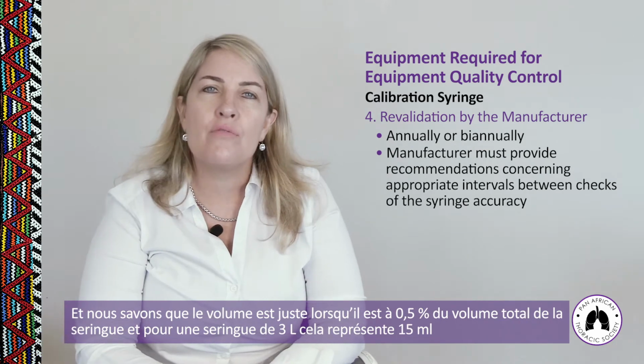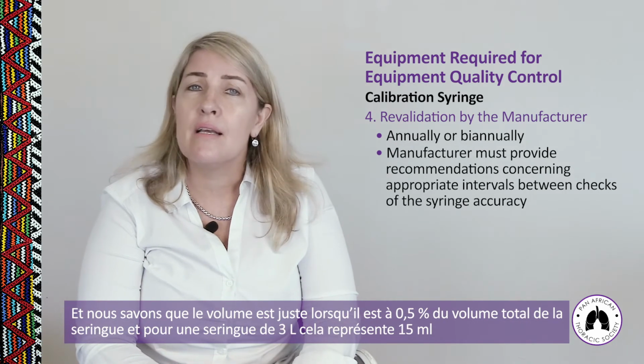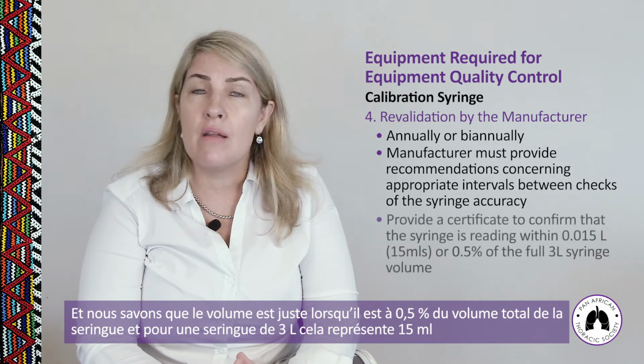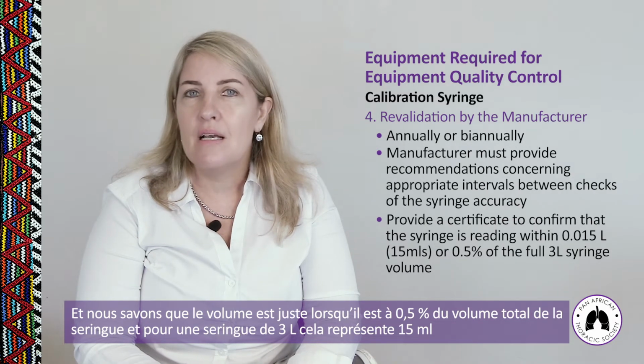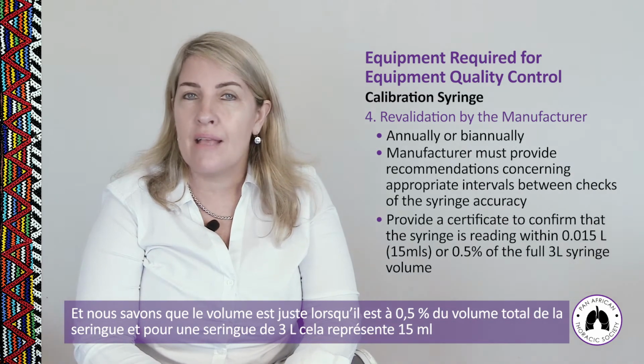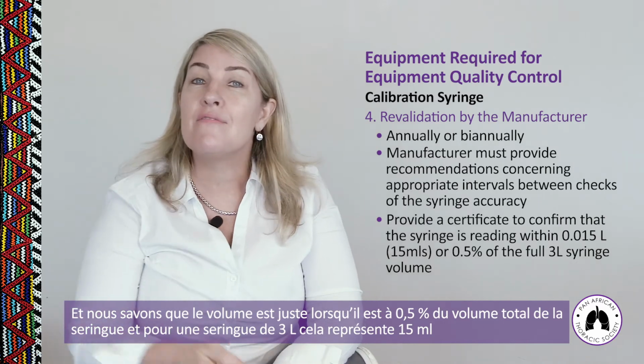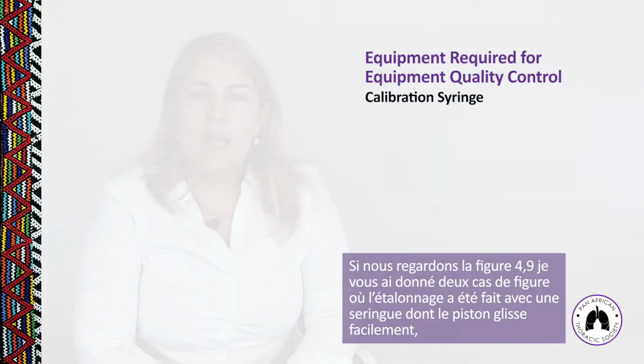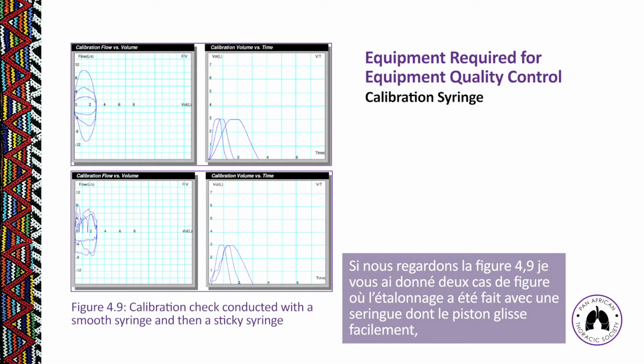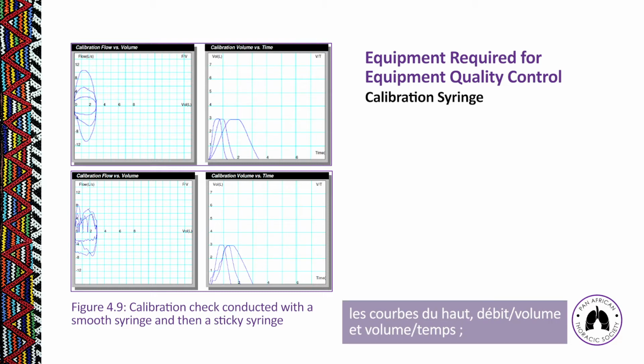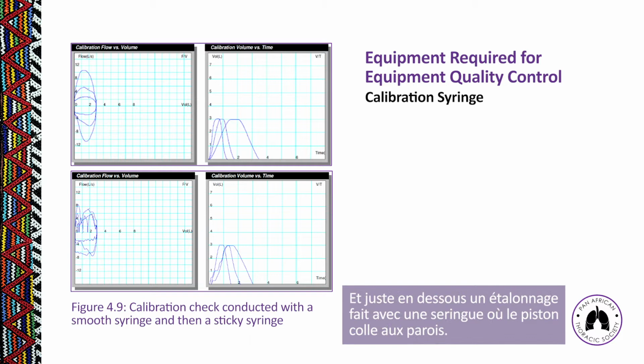And we know that a syringe volume is reading accurately when it has a volume of within 0.5% of the syringe volume. And in the case of a 3-liter syringe, that's 15 milliliters. If you look at figure 4.9, I've given you two different scenarios of a calibration check done with a smooth syringe. That's the top graph, flow volume and volume time graph. And then just below that, you can see a calibration check done with a sticky syringe.